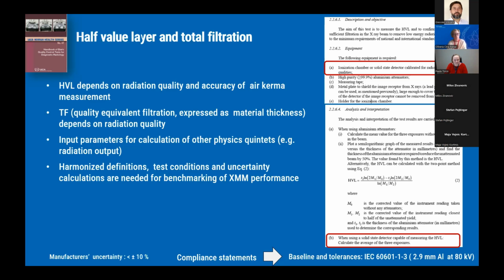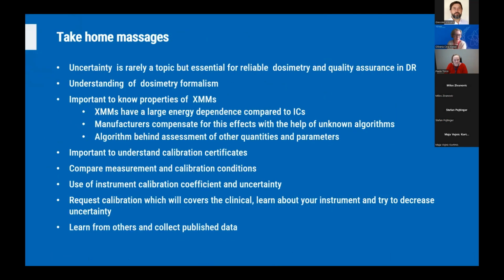And just for your information, the Handbook of Basic Quality Control Test also states that HVL measurement is one of the mandatory QC parameters and allows for use of two methods. One is based on the ionizing chamber and aluminum filters, and the other one that is, I would say, mainly used in clinical environment is based on the use of XMMs to measure half-value layer, again, for the same reason that I mentioned in the case of the tube voltage and exposure time. Uncertainty of the HVL is very important in the clinical conditions for the sake of the compliance statements that medical physicists have to make.